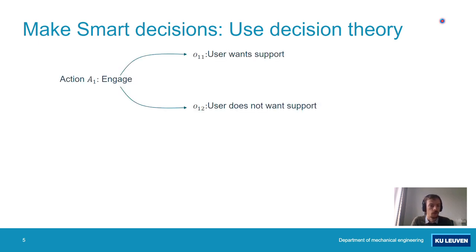Once the exoskeleton has recognized the motion, it now needs to make a decision about whether to engage the support mechanism or not. To do this, we use decision theory. This means we first think of the actions the controller can make, as well as the outcomes or situations we can end up with. The first action is to engage the support mechanism, which can result in either the user getting the support they want — a positive situation — or the user not wanting support but getting it anyway, in which case the exoskeleton is hindering the user. To both of these situations, we assign a utility or usefulness score: a positive score for the positive situation and a negative score for the negative situation.